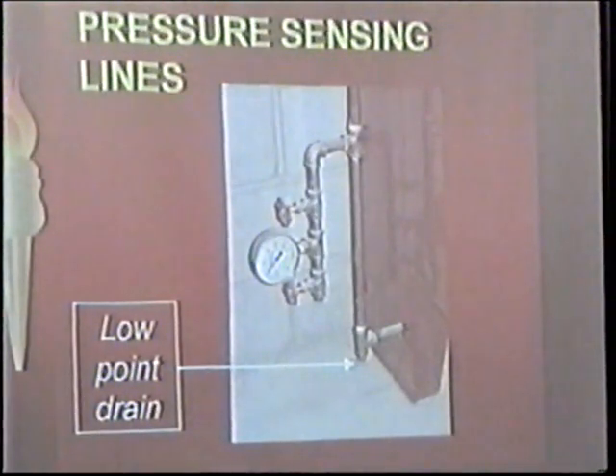This is sensing lines, and again, it's a housekeeping issue for down the road. But, you know, it's kind of nice when this drain line gets put up high so that the customer can get a bucket under it when they do their weekly testing. But if you do that for them, I'm going to ask for a low point drain down here at the bottom, because when I go to drain that pressure switch, I don't want to have 4 feet of half-inch pipe water coming up inside the controller when I take the pressure switch. Just a little bit.